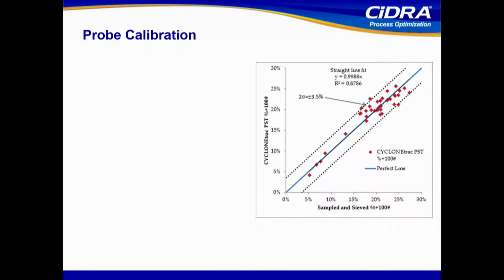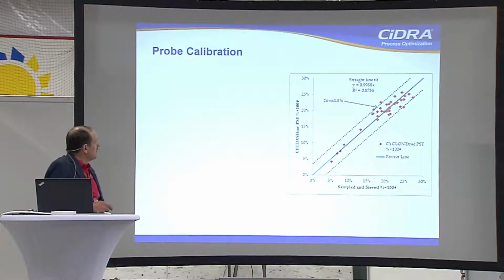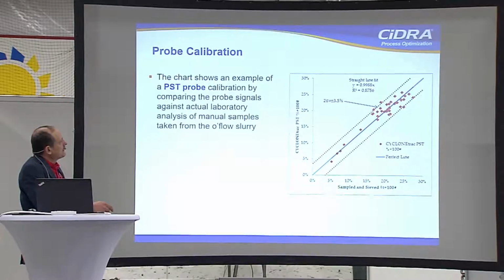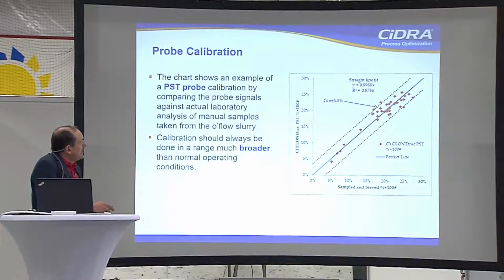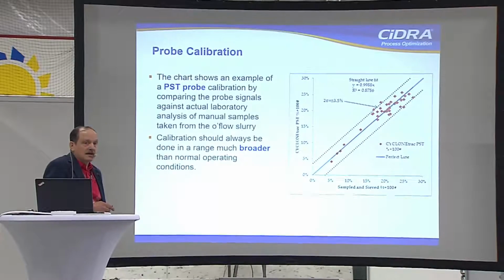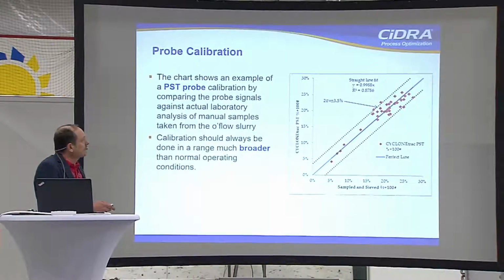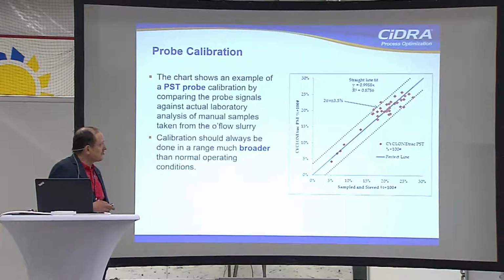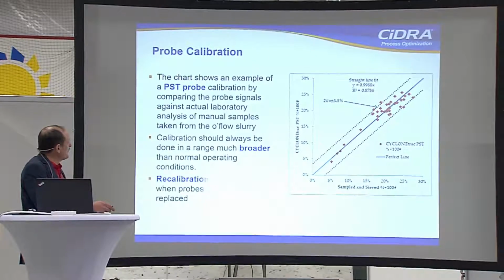This is how probe calibration typically looks. It would be preferable that this calibration sampling would be taking place at a broader range than the typical optimized operational point only, because the wider the range, the more accurate the model. Of course, the accuracy is also improved by the number of samples, and it's also affected by your lab reference accuracy. So that's the total sum of those.